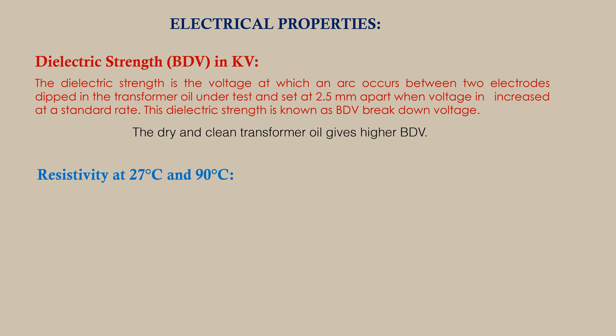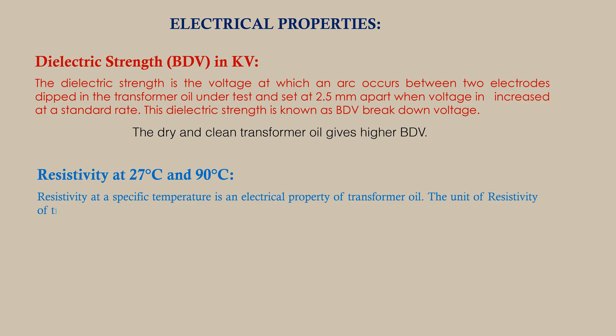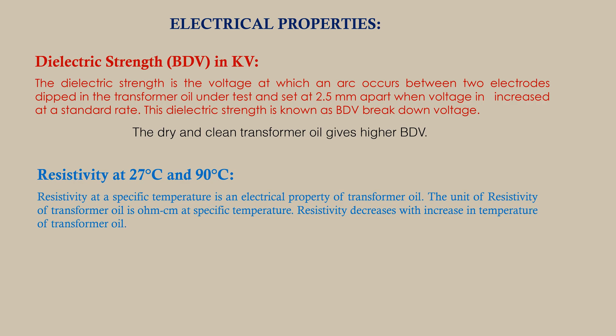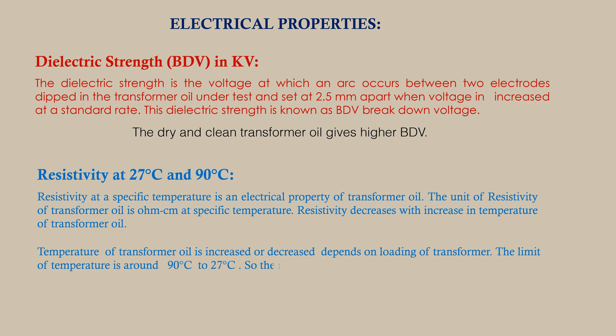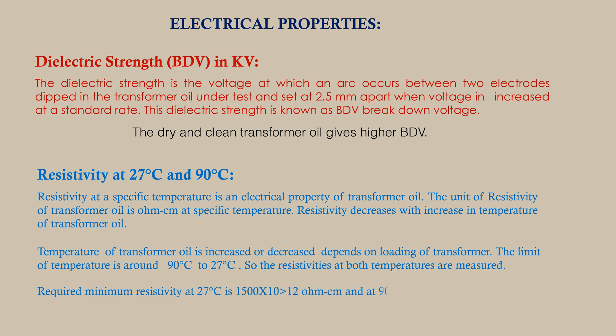Resistivity at 27°C and 90°C: resistivity at a specific temperature is an electrical property of transformer oil, with units of ohm·centimeter. Resistivity decreases with increase in temperature. The temperature of transformer oil increases or decreases depending on the loading of the transformer. Since the temperature range is 27°C to 90°C, resistivity is measured at both temperatures. The required minimum resistivity at 27°C is 1500 × 10¹² ohm·cm, and at 90°C is 35 × 10¹² ohm·cm.